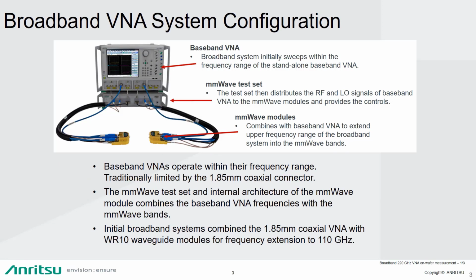So this is the basic configuration of a broadband VNA system. We start off with what we call a baseband VNA, which is the VNA that operates up to the frequency limits of the test port connector, which for the higher frequencies will typically be a 1.85 millimeter test port. And so the 1.85 millimeter or V connector test port will limit the baseband VNA to 70 gigahertz.